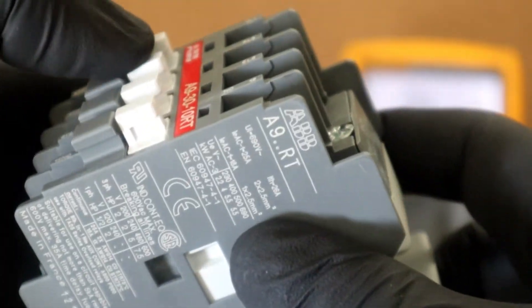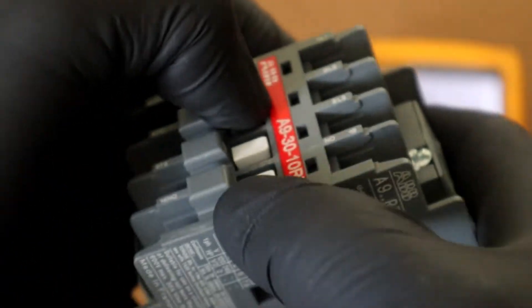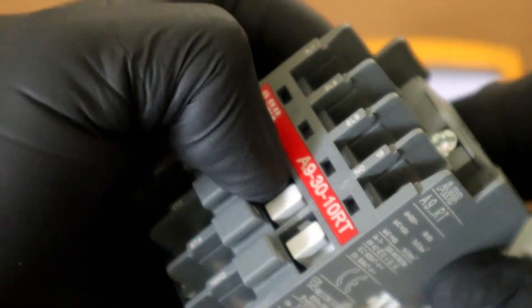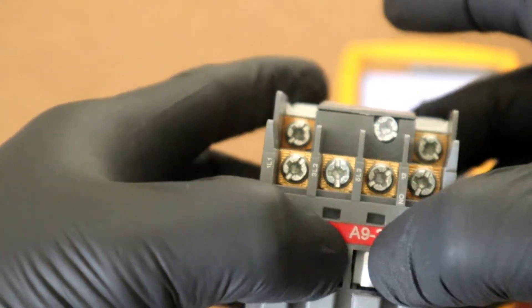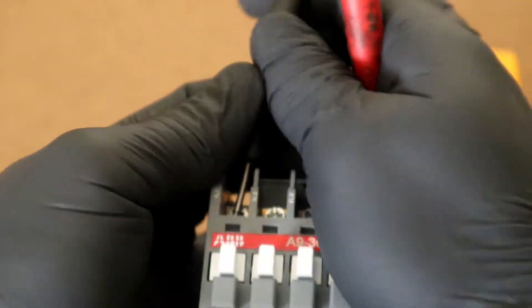To simulate a closed operating position of our contactor we physically depress here with our fingers and carry out another set of ohm readings. Or you can do a continuity check but I'll do the ohm readings.